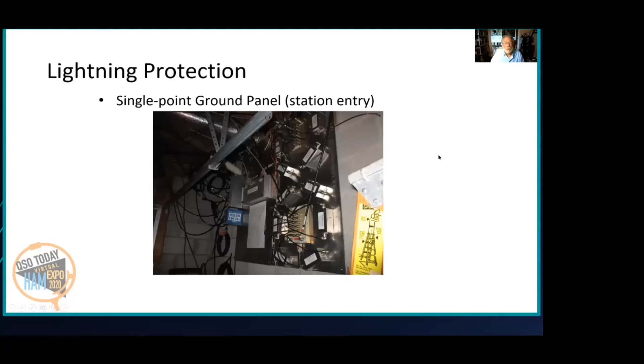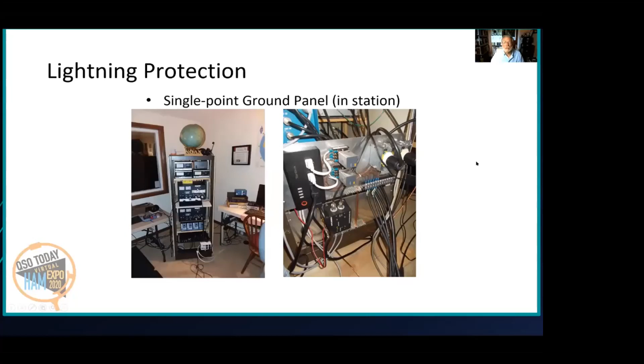You can see a ground wire here. Here's a big metal panel. Each one of the stations, there's a station here, there's a station here, is connected to the single point ground panel with these big heavy number 6 wires. And then there's a big heavy number 6 wire that goes outside to the perimeter ground, which is right on the other side of this wall.